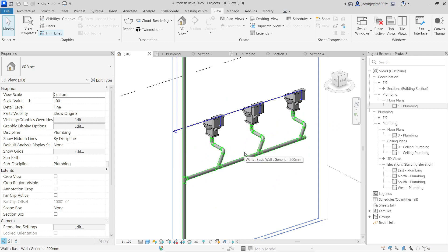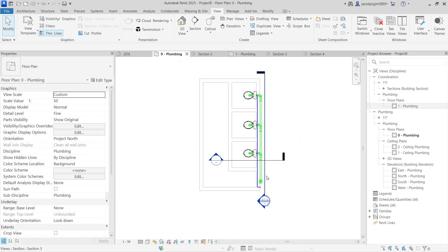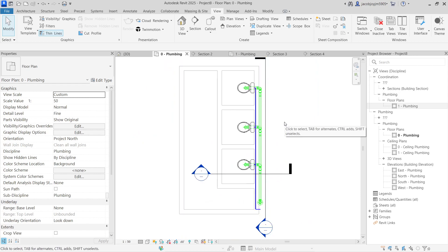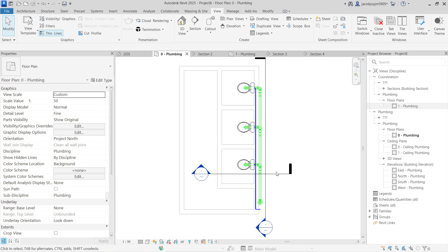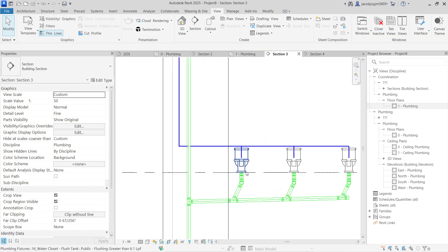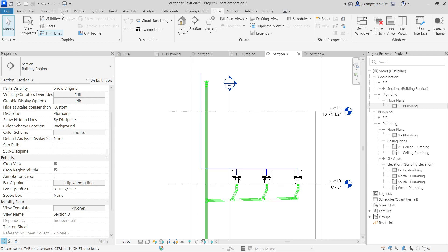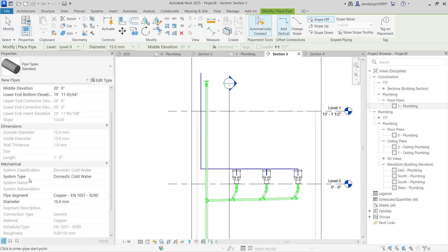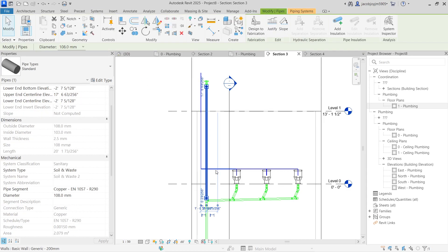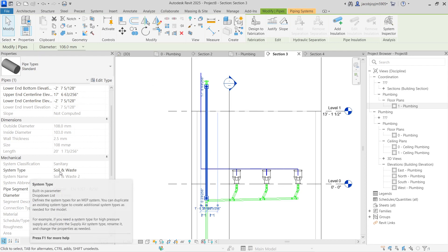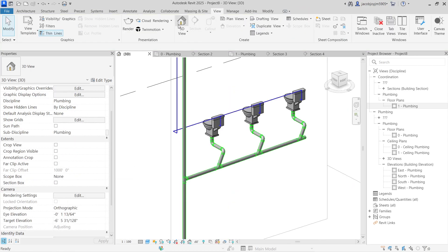This is how you have to draw the pipe routing. The main takeaway is: you need a section to draw vertical pipes. Draw the horizontal layout in the plan, take a section, and draw the vertical pipes. When drawing the pipe, take care of the system classification. Always check the system type before drawing. Also take care of the pipe type and diameter. Even after you model the pipe, you can change the pipe type or system type — no issue at all.